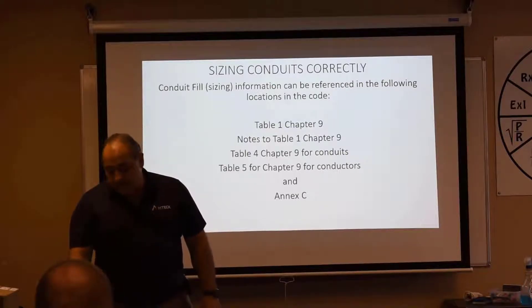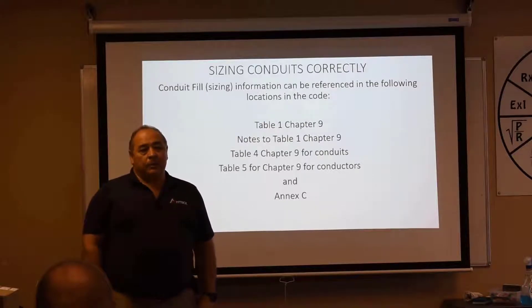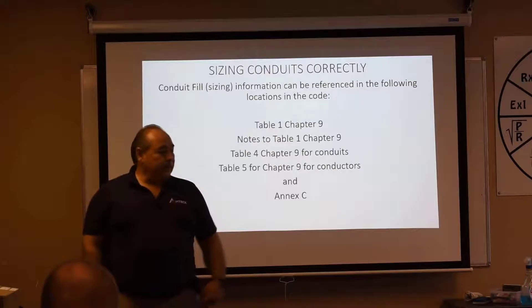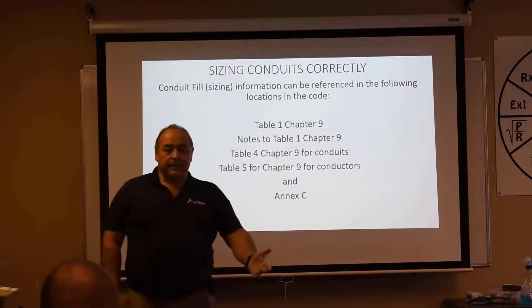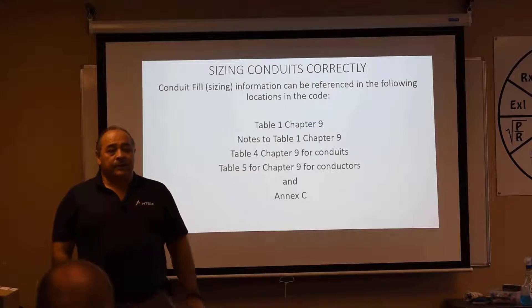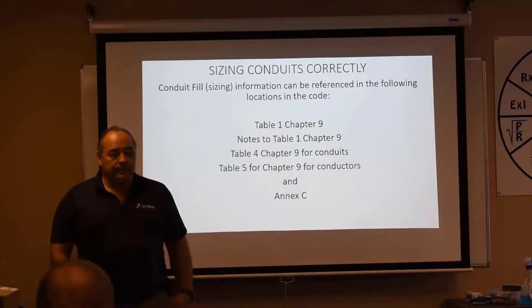Here's the problem with using the NEC: a lot of conduit systems might have multiple different types of raceway in one conduit run. We might have some PVC underground, some rigid above, some EMT above the ground, and maybe some flexible along the way. Each one of those conduit systems has its own interior space.